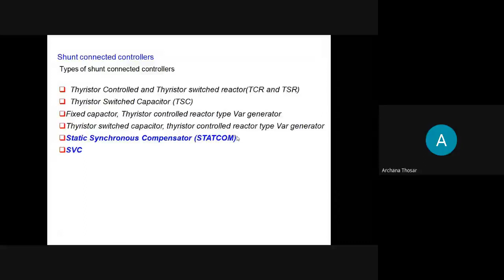Another point that will come to your mind is where should I place this FACTS controller? Now I have selected that I will go for a shunt type of controller. So I will connect it in parallel to the line. I will be injecting a current which will be in phase quadrature to the voltage, and thereby I will be mimicking the reactive power compensation. So now I will see where I should keep this FACTS controller. So the best point is the midpoint location. So best is the midpoint.